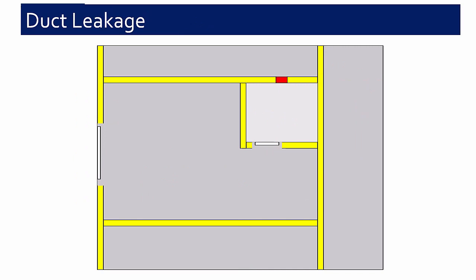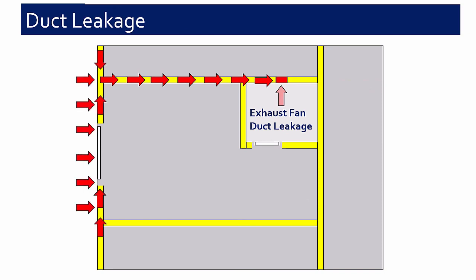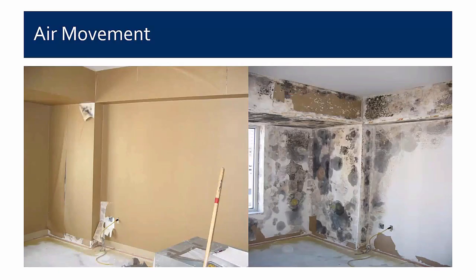Another situation comes from duct leakage. With the same exhaust fan example, if the duct is leaking air through the ductwork, the entire wall can act as a duct. If the duct is located in the wall, leakage at the joints pulls air from the wall — potentially pulling air from outside or, in the case of reservoir cladding, from the brick cavity space. This example had vinyl wall covering. When the vinyl wall covering was pulled back, the upper soffit was acting as an unintended duct — the bathroom exhaust leaking through the joints was pulling air from the wall through that soffit.